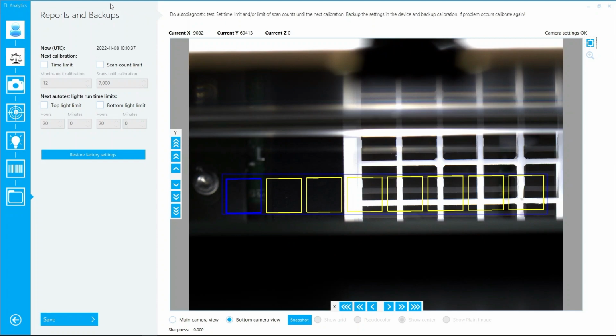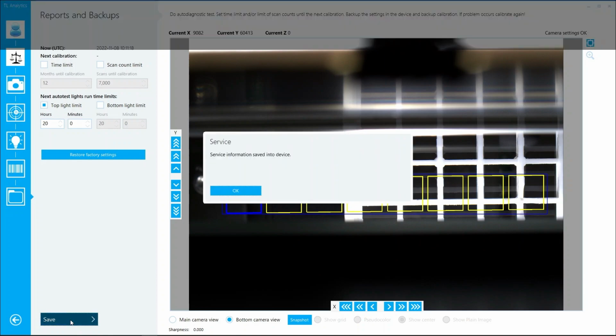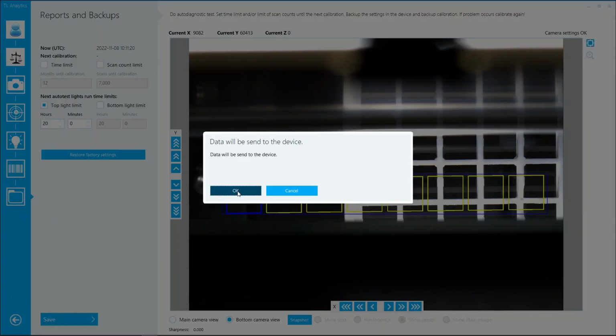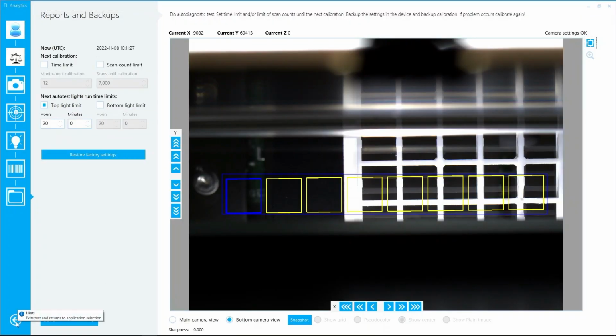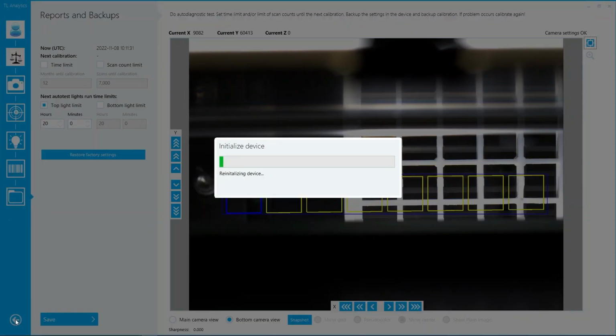So the last step of the calibration is reports and backups. All you need to do at this step is to check this box and set the top light limit to 20 hours. This means that after 20 hours, the auto-diagnostic process will be required. Now click Save to finish the calibration process. Now click on this arrow to exit. Exit and return to application selection. Now the device is reinitialized and we're at the end of the whole calibration process.